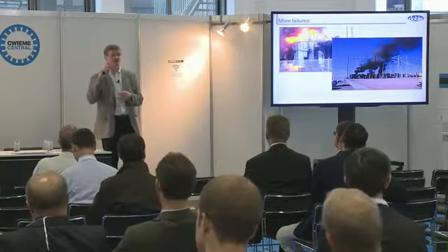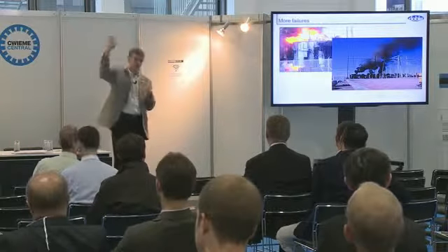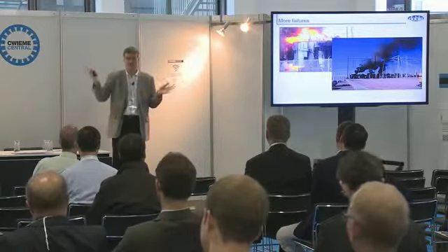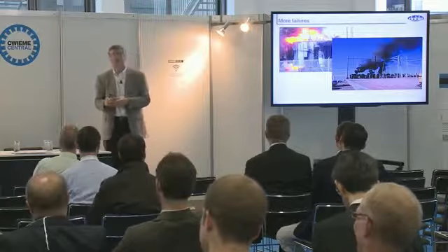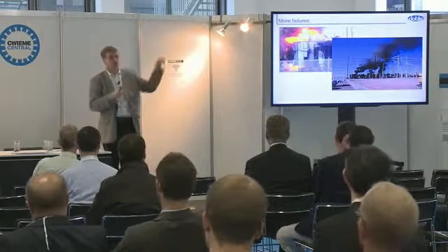And it failed because a snake crawled up the bushing, caused a flashover, bushing failed, transformer followed. Oil from that failure went into the cable tray, moved along to the next transformer, took that transformer out. One snake took out 4 transformers. It's in Arizona. How much condition monitoring do people sell for snakes? Do you have a snake monitor?